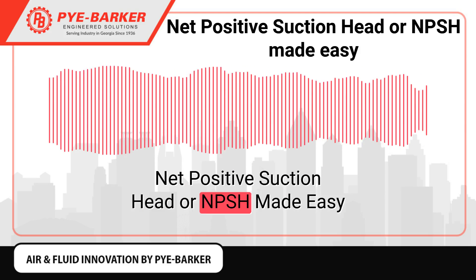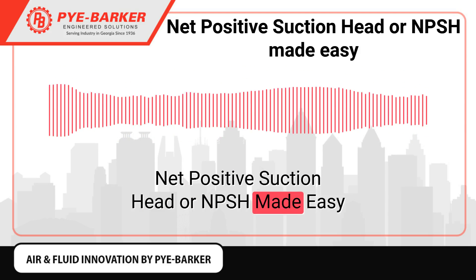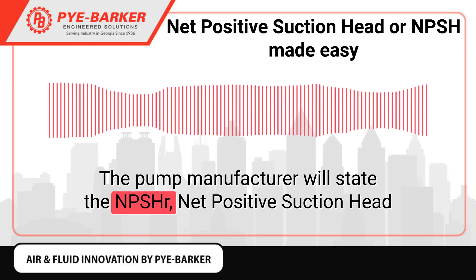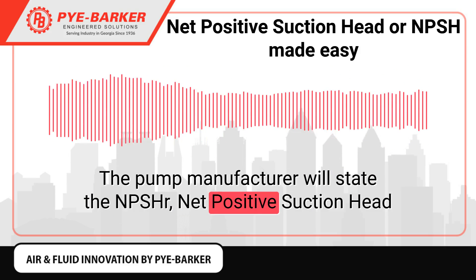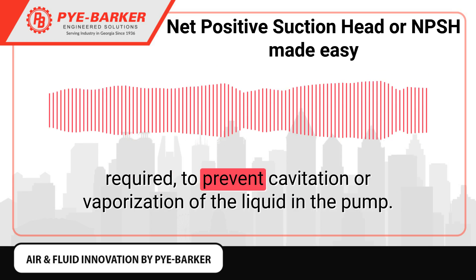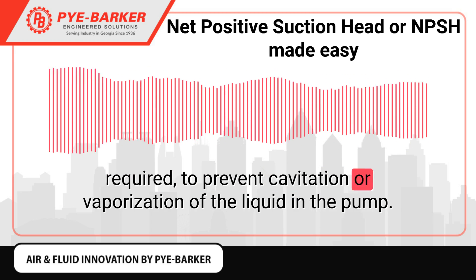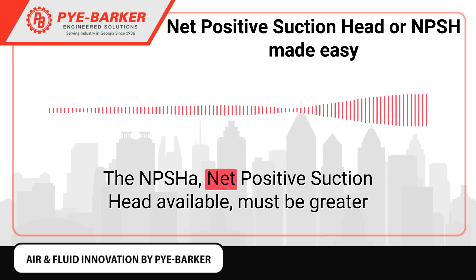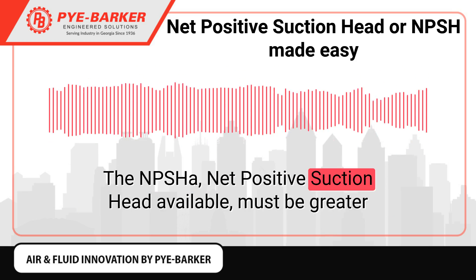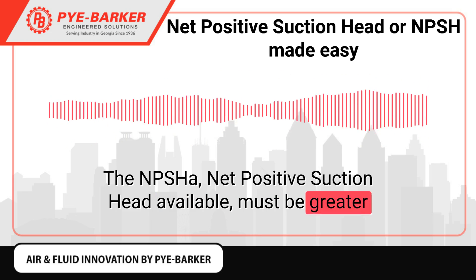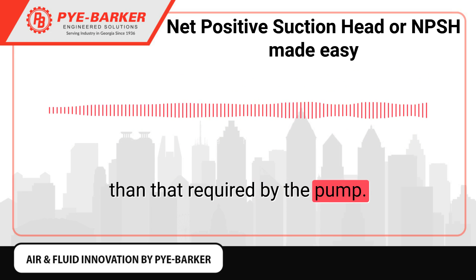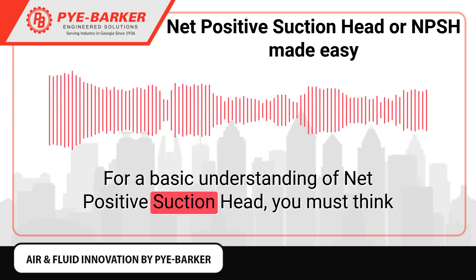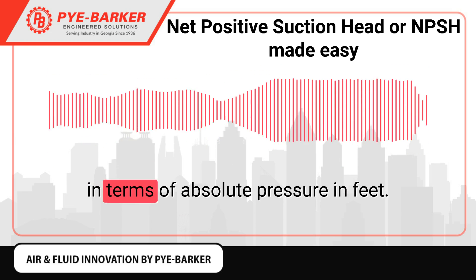Net Positive Suction Head, or NPSH, made easy. The pump manufacturer will state the NPSHR — Net Positive Suction Head Required — to prevent cavitation or vaporization of the liquid in the pump. The NPSHA, Net Positive Suction Head Available, must be greater than that required by the pump.